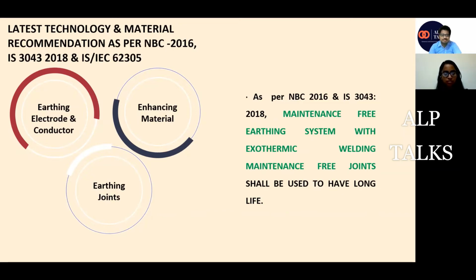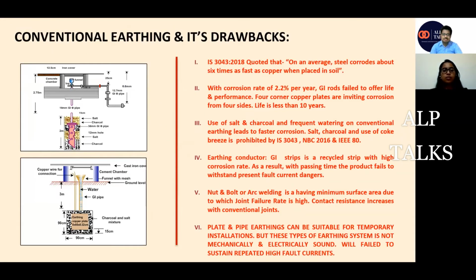So here I was telling you about the latest technology and material only, which was recommended as per the National Building Code, as per Indian Standard IS 3043, as per IEC 62305, which is a lightning protection standard. So basically, all these standards recommend using a maintenance-free earthing system with permanent joints, because joints play a very important role when it comes to the earthing system. So they recommend permanent jointing like exothermic welding in place of nut and bolting or arc welding. So we'll discuss all these things one by one.